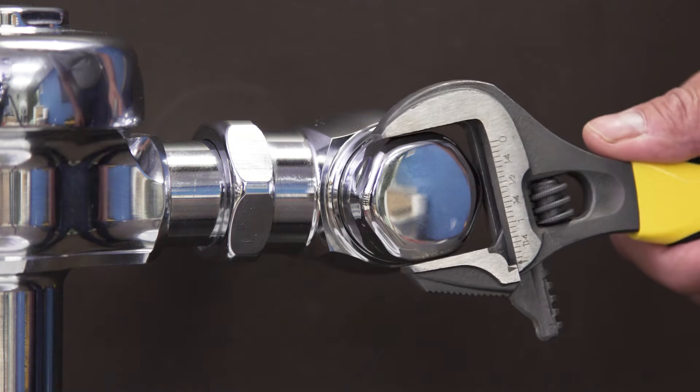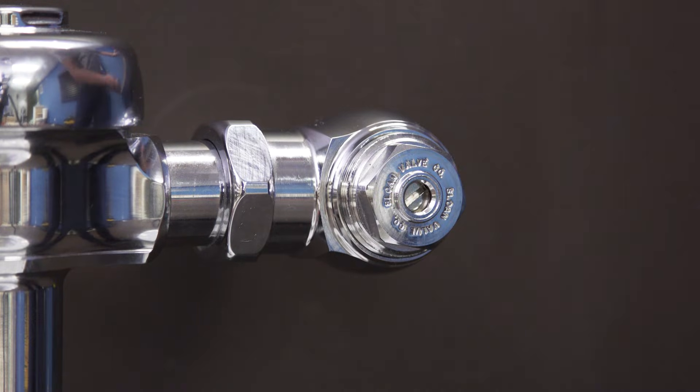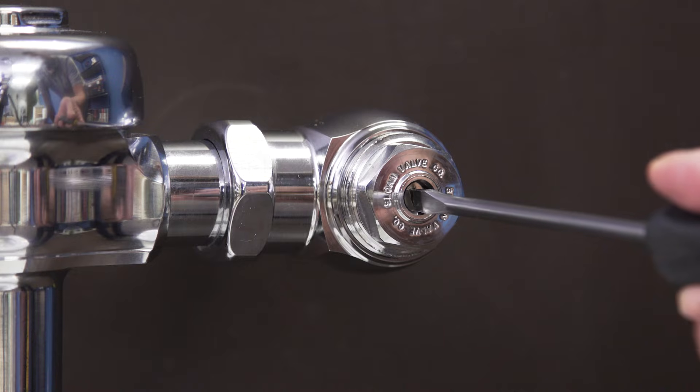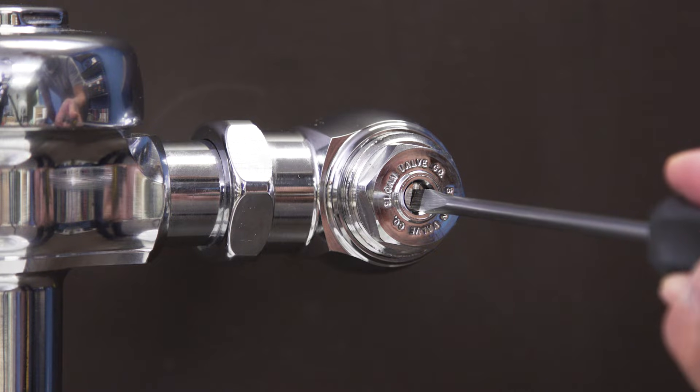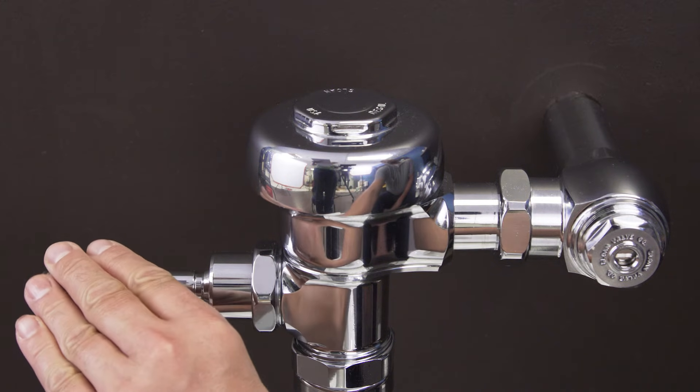First, shut off the water to the flushometer. Remove the cap and use a flat blade screwdriver to turn the screw clockwise until the control stop closes. Next, hold down the handle to remove any remaining water.